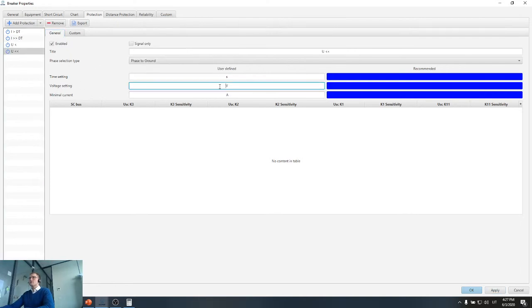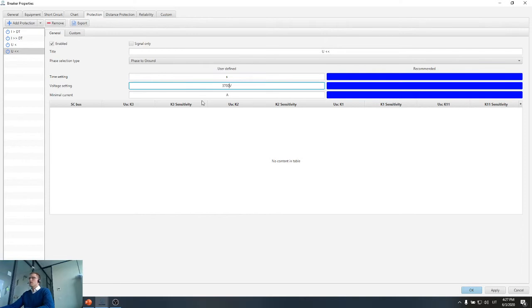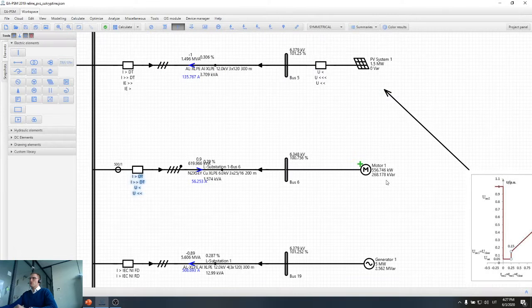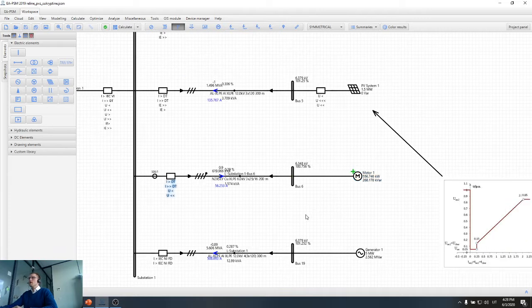Then for the next stage we will set an even lower voltage, let's say a 40% voltage drop, so the voltage will reach 3700. In this case of high voltage drop, our tripping time should be faster, let's say 3 seconds. So 3 seconds will provide enough time margin for overcurrent protection devices to operate. If the overcurrent protection devices don't operate, then after 3 seconds the motor will be automatically disconnected to avoid high inrush current after motor acceleration.